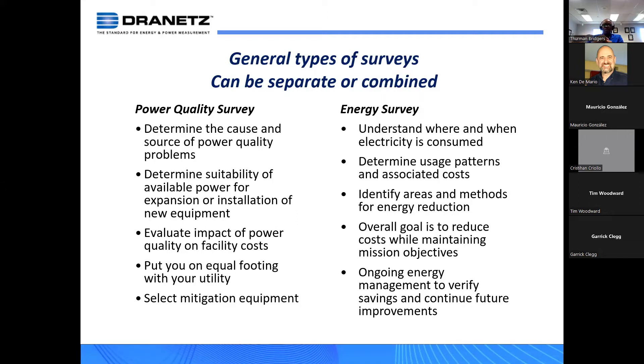Evaluate the impact of power quality on facility costs. Another reason is to put you on equal footing with your utility. In power quality applications, we see a lot of finger pointing. When the lights flicker, the first thought is usually that the utility is doing something on the grid, but statistically it's probably within the building itself. Having documented information means that if the instrumentation says the PQ problems are generated by the utility, you can go to your utility account representative with documented evidence.